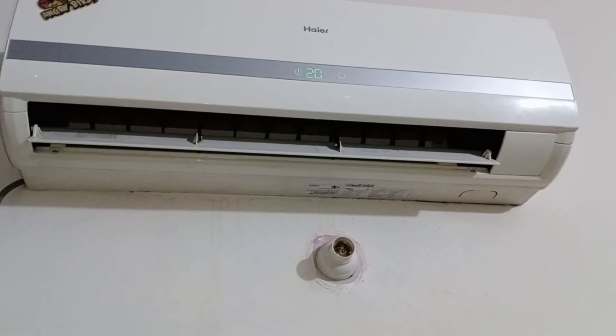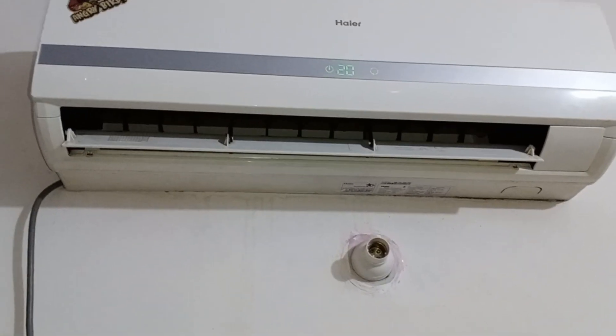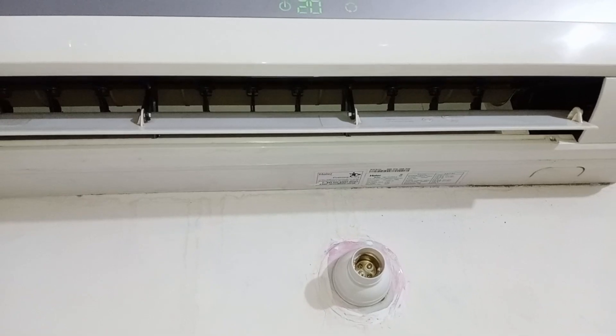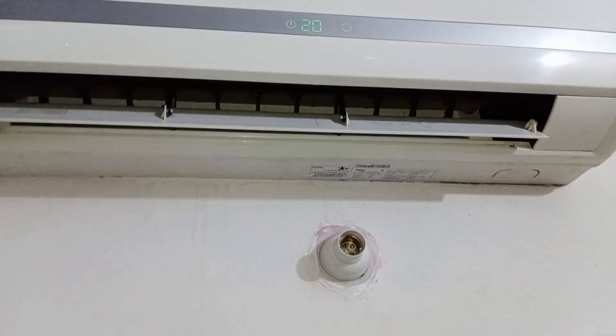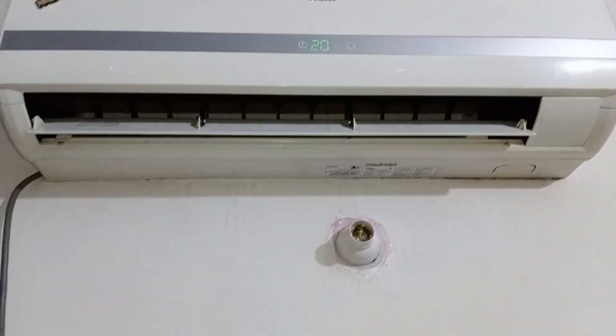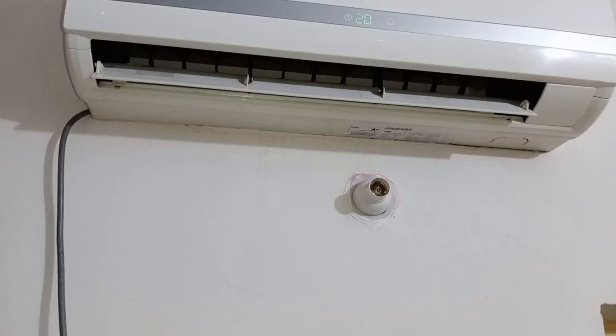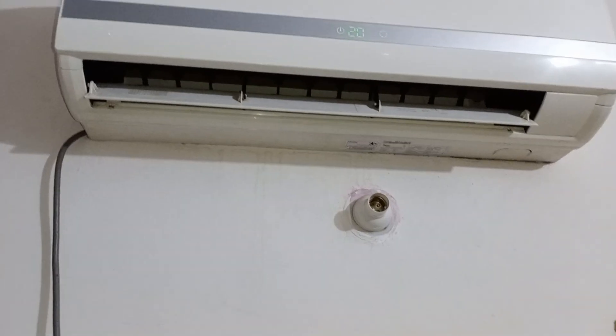First, let's talk about the non-inverter air conditioner. The customer sent us pictures showing ice forming on the suction pipe. They explained that initially the AC provides cooling, but after a while the airflow becomes significantly reduced.